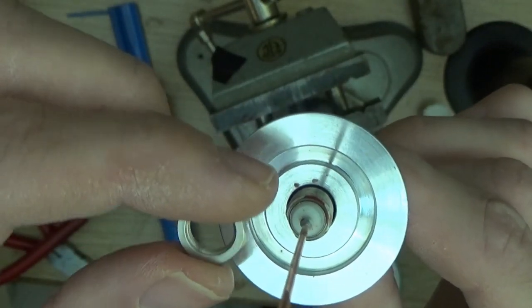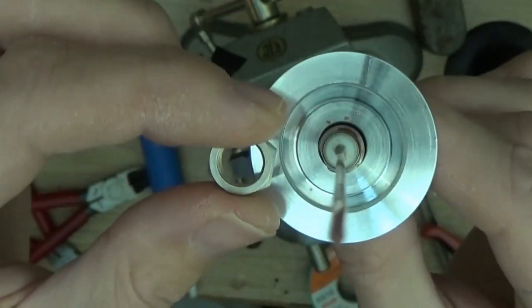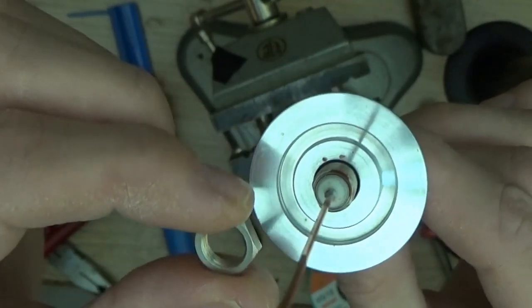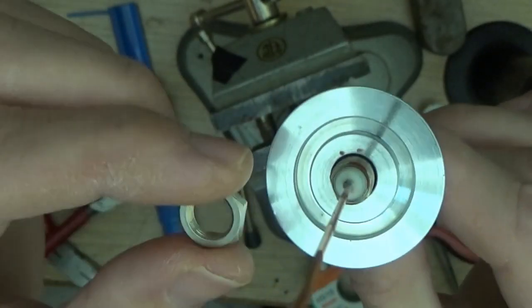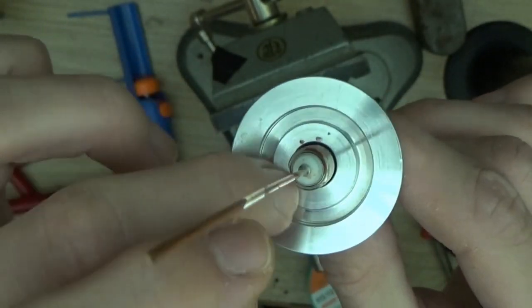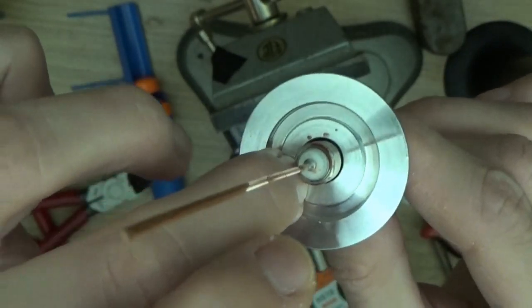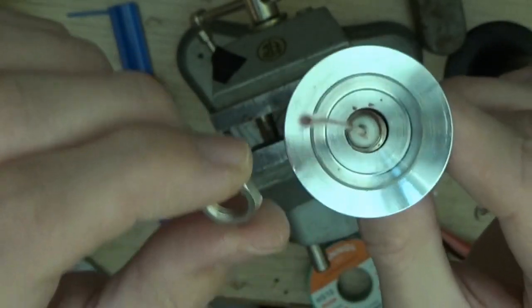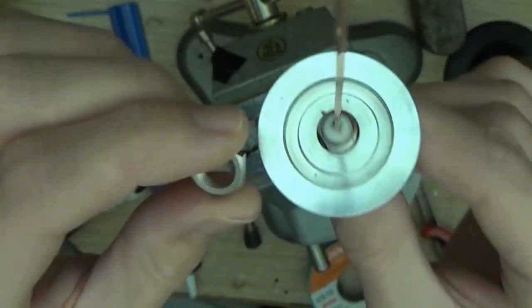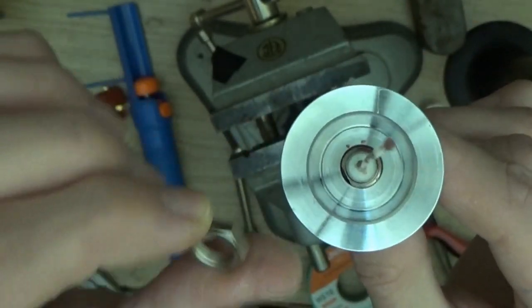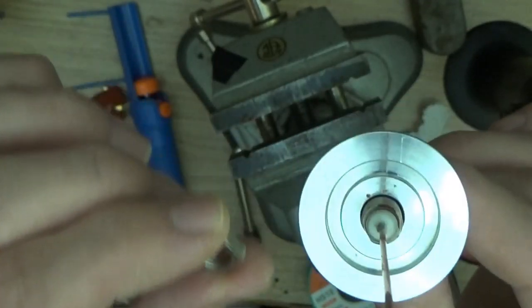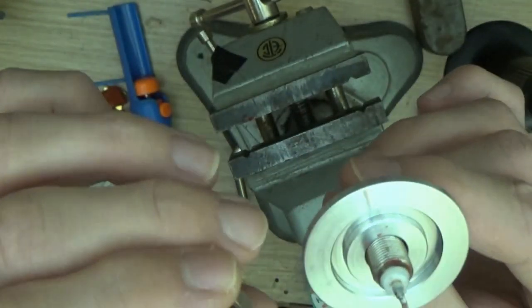Now, if we fit a nut on here, then we are going to have a very, very long leakage path out of that space, which means that once we pump down our chamber, the pressure in that will take forever to diffuse out. This is called a virtual leak. It's a leak to an entrapped place in the system. And we need to deal with this or this will be a terrible experience.